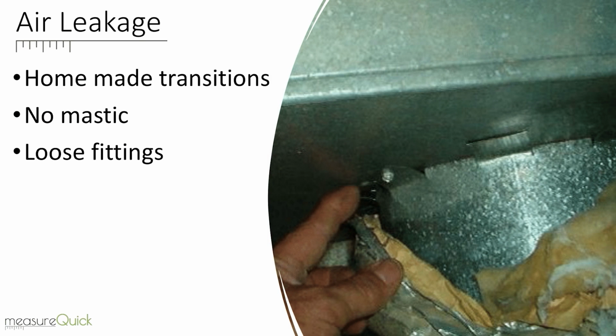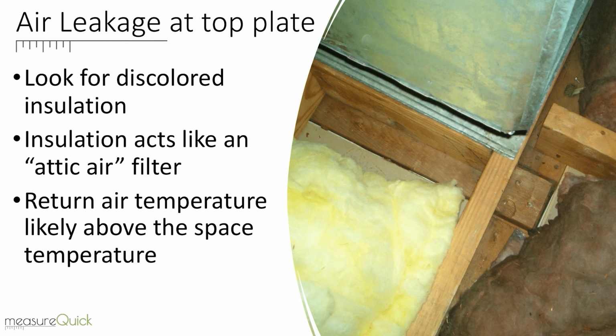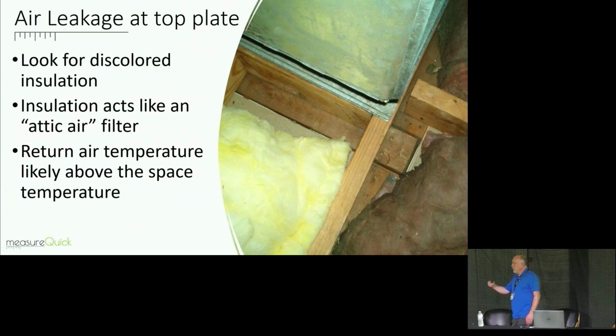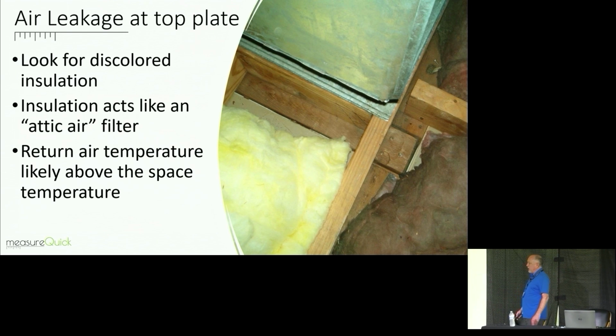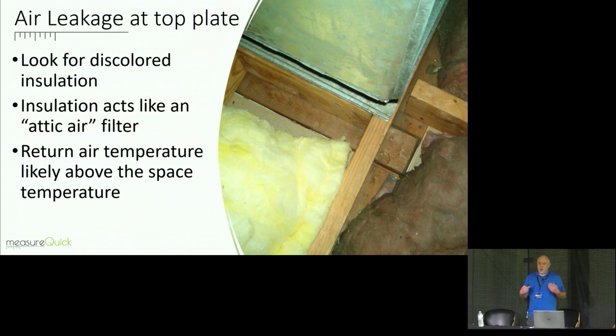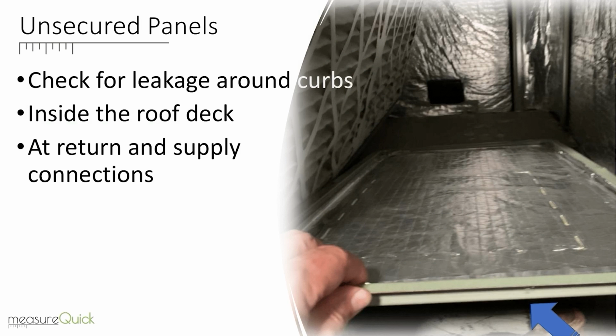Homemade transitions, no mastics, loose fittings, air leakage issues. Air leakage at the top plate. This is very, very common where somebody's framing in a return. You'll notice that the insulation on the one side there is almost black, and it's because it's become an attic air filter, right? We're pulling return air through from the hot attic space. Again, erosion of the temperature split on the system, right?